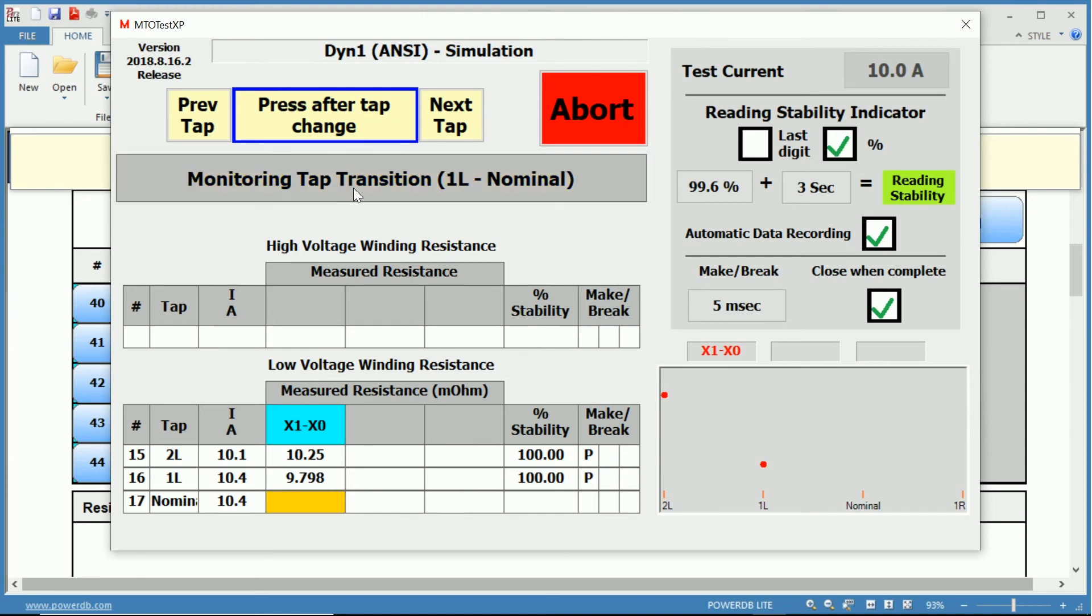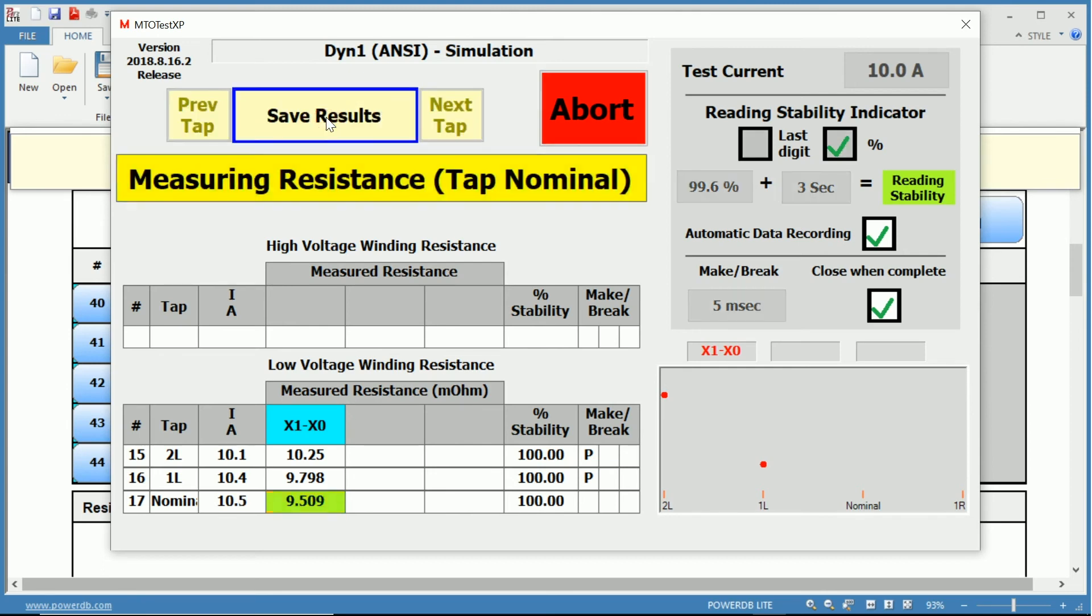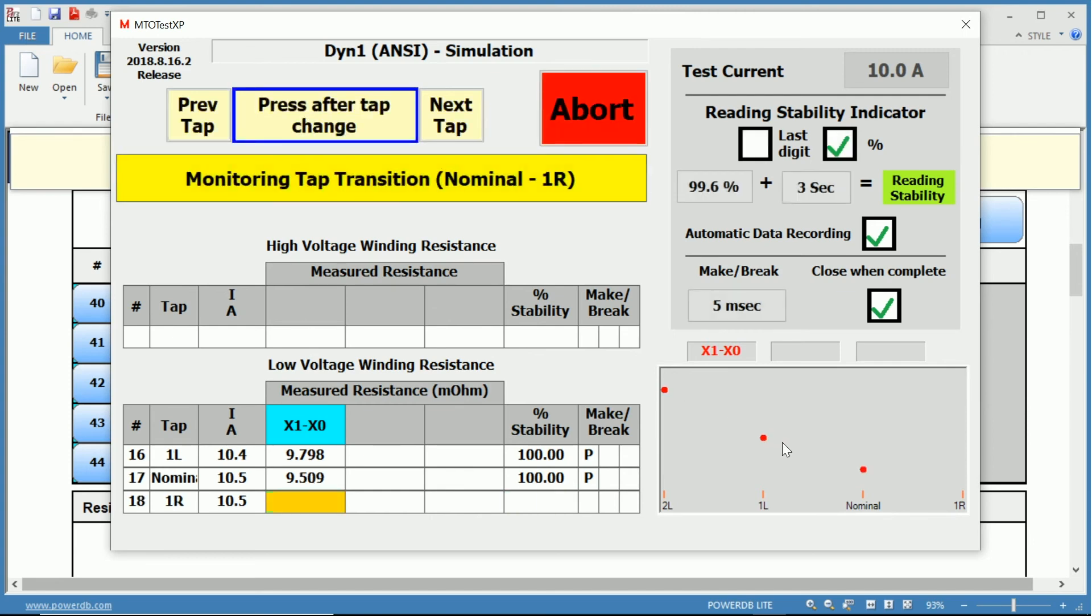And now we are charging and measuring the resistance of the next tap. Again, monitoring the tap. Once the measurement is completed, we change the tap and we press after the tap change, initiating the next test. Again, our plot is updating with the resistance values.